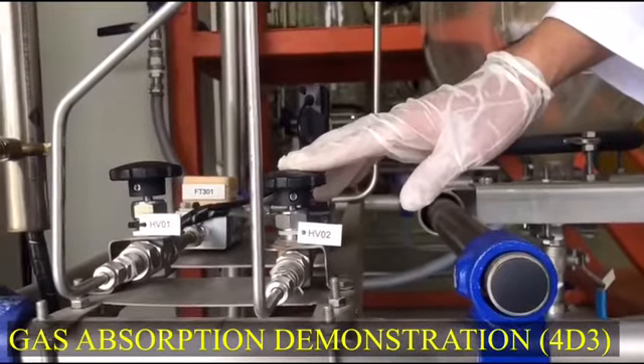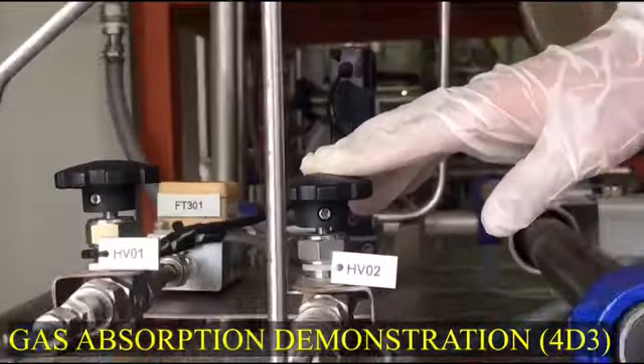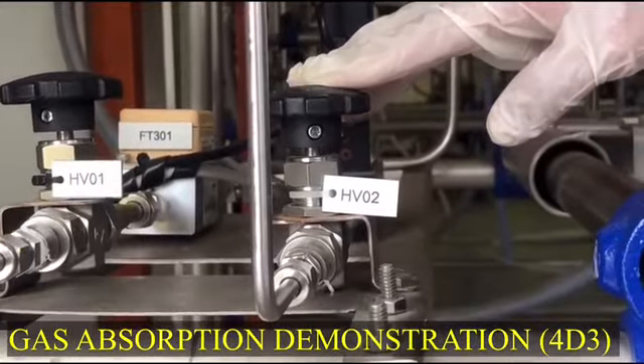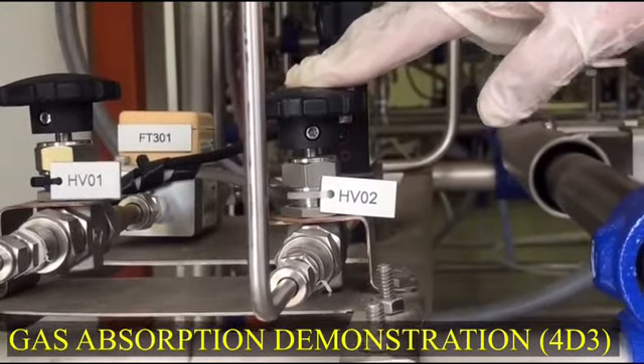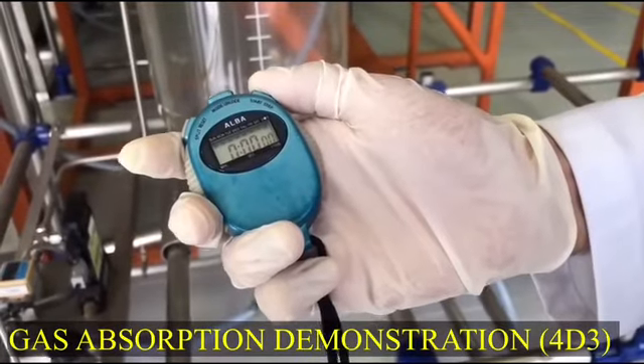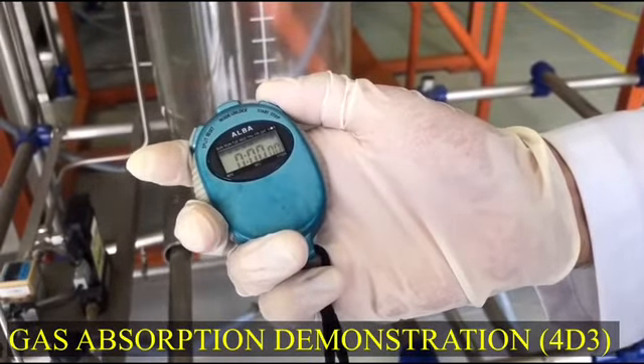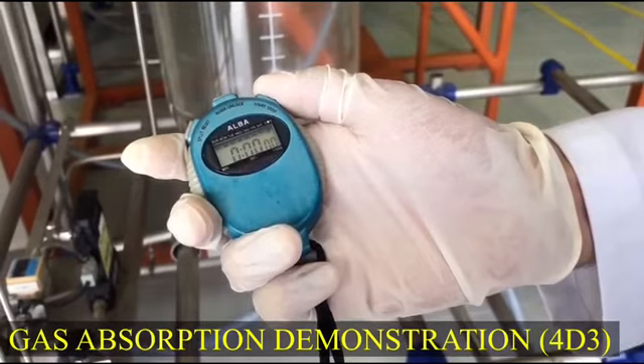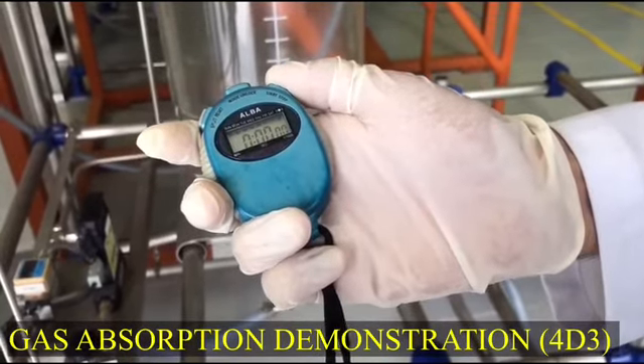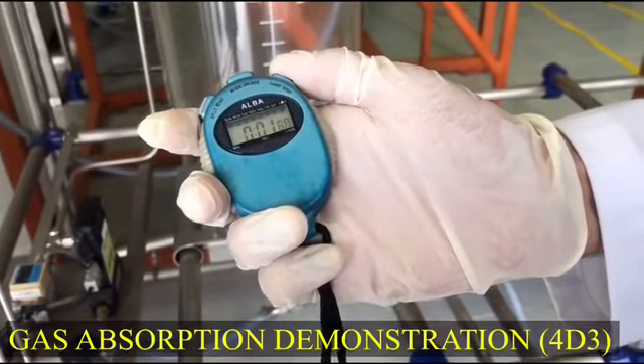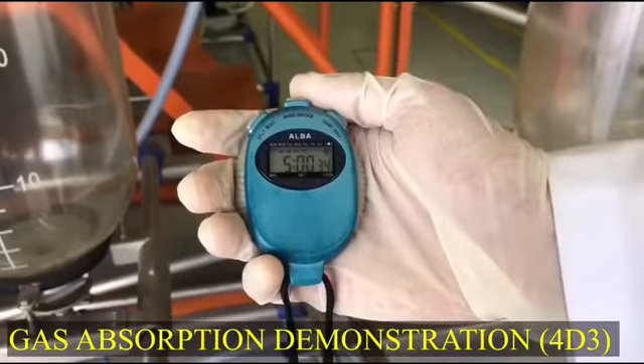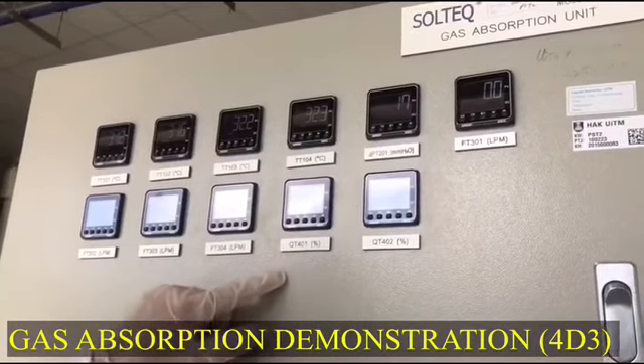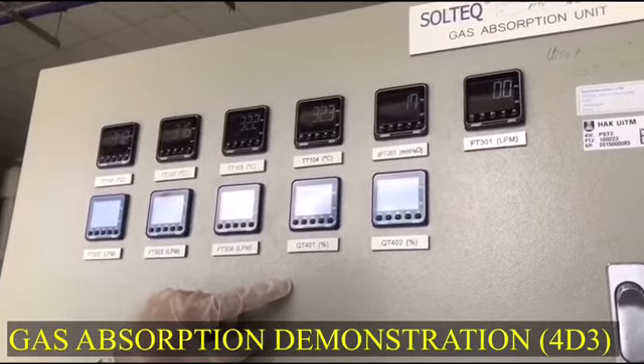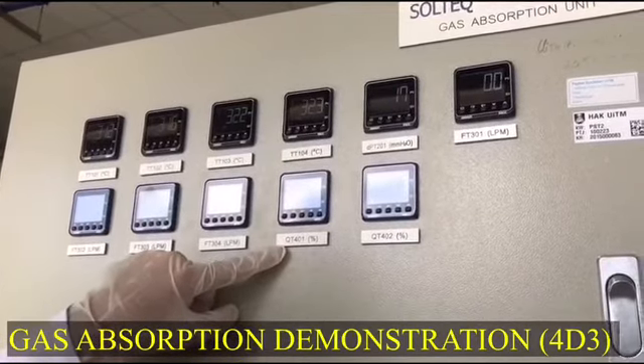Open and adjust valve HV02 CO2 supply to give a flow rate of 3 litre per minute. Immediately start the timer and collect the sample at 5-minute intervals until there is no more change in CO2 composition over time, the steady state. At the same time, record the outlet CO2 composition at QT401 on the control panel.